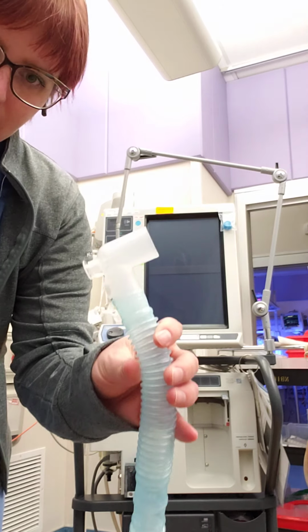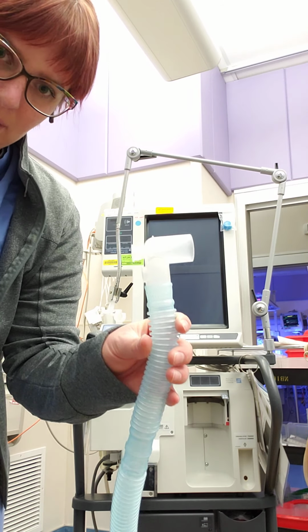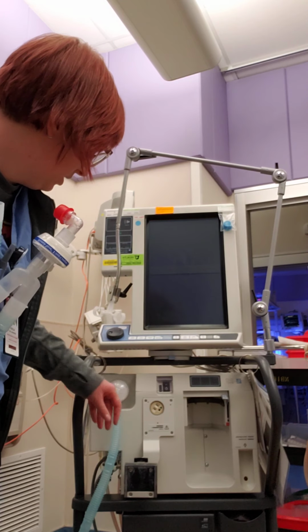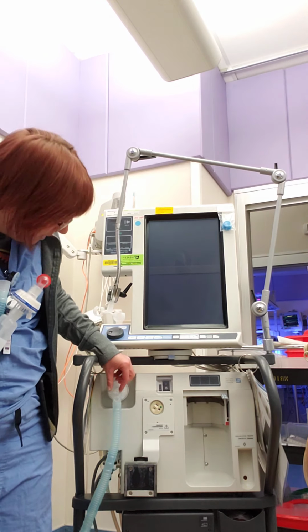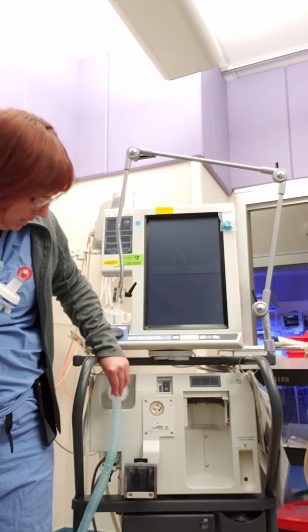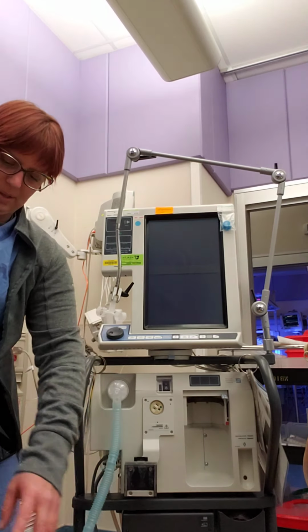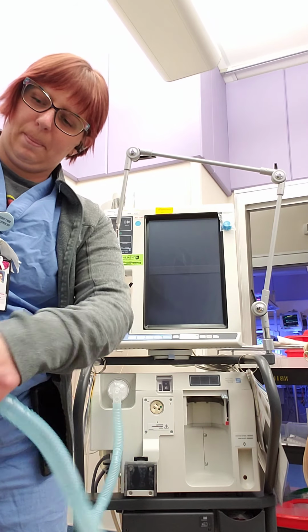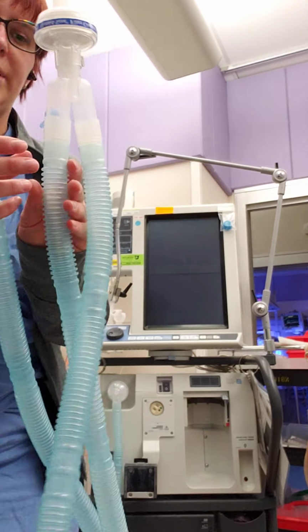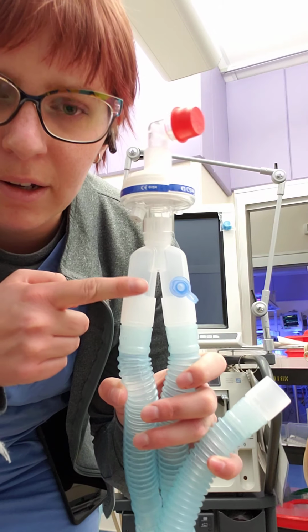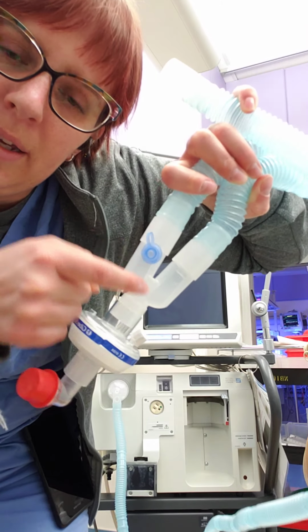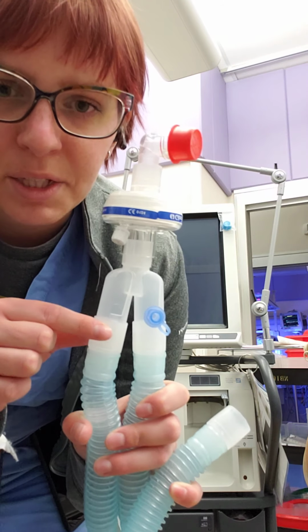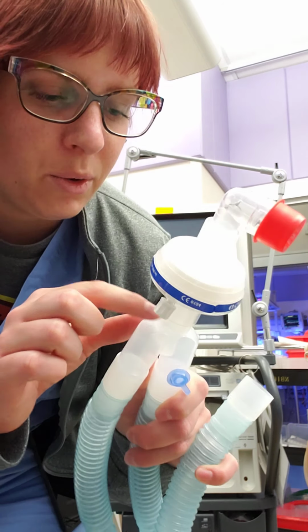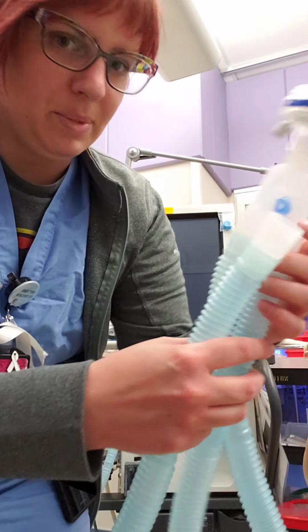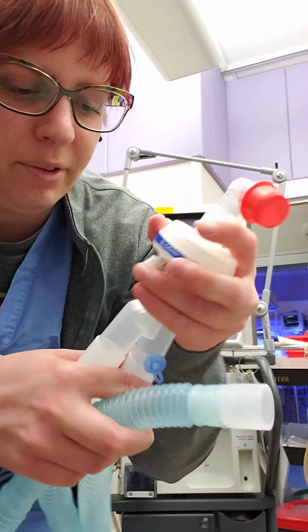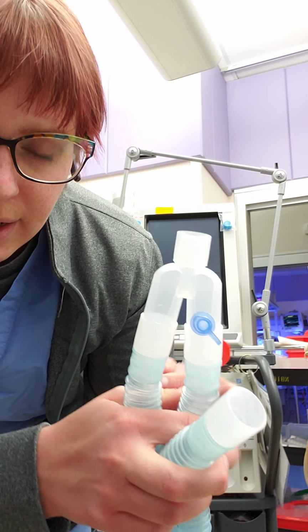Next we take, remember, the inspiratory limb that goes to the patient. Remember, the patient's breathing in, and we hook it to the viral filter as such. One thing to be cautious about: if you feel a leak, this little cap can come undone. There's a little cap right here. It can come undone. Just be careful of that. That's a common occurrence. We follow our inspiratory limb up, and we come to what we call the Y. This is called the Y of the ventilator. As you can see, it's kind of shaped like a Y. So if you hear something referred to as the Y, this is what it is. This is where the inspiratory and expiratory limbs meet in order to connect to the patient. So our inspiratory limb comes up and meets at the Y. And then we have our one single connection right here that connects to our patient.